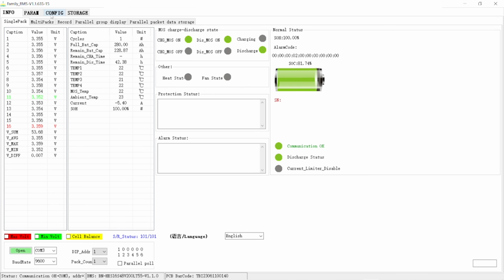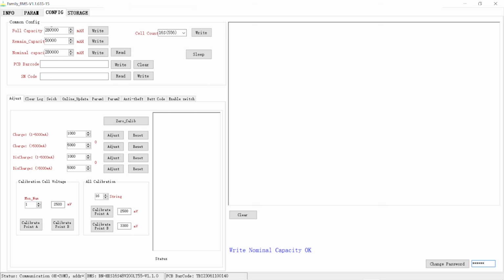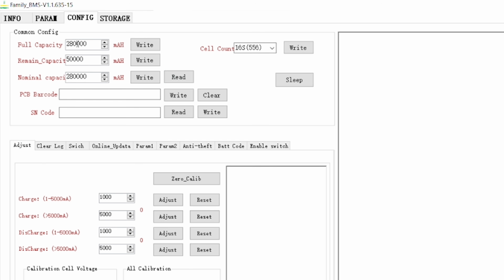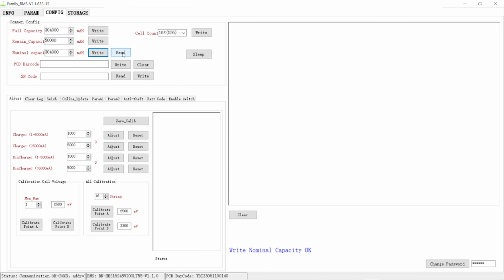In the BMS software, I click on Config and enter the password, which is 888888. Now I'm able to modify the basic settings. I change the full capacity setting to 304 amp hours and hit the Write button, then change the nominal capacity to 304 amp hours and hit the Write button. Then I click the read button to make sure the settings were applied, and I can see they were.